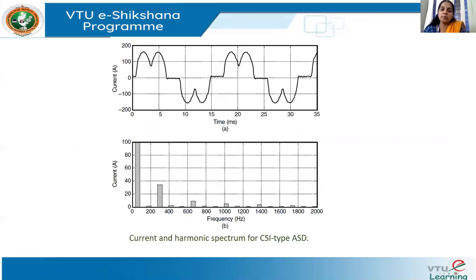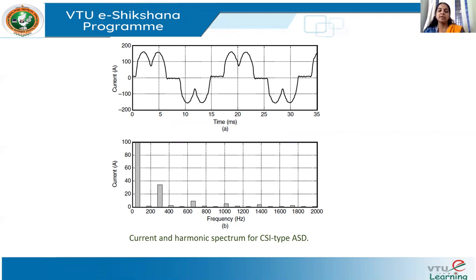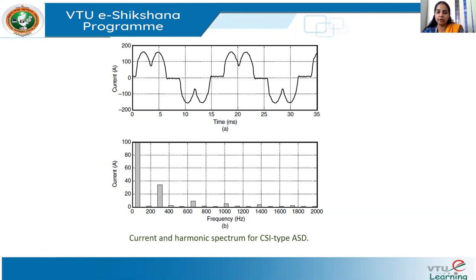The first waveform shows the current produced and its harmonics in three-phase converters. This is an example of a current source inverter (CSI) type adjustable speed drive with a three-phase converter. You can see the third harmonic component is completely eliminated. The fundamental at 50 or 60 Hz is present, and at 150 or 180 Hz (third harmonic) it is almost negligible. The fifth harmonic is present, but the ninth and other multiples of three — the triplen harmonics — are almost eliminated. The system still generates harmonics in terms of the fifth, seventh, and other higher harmonic components.